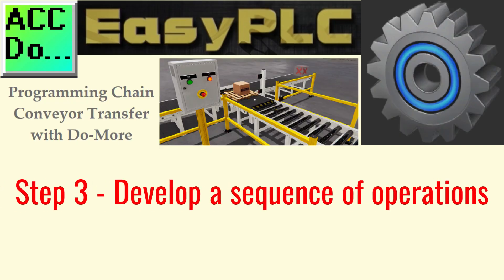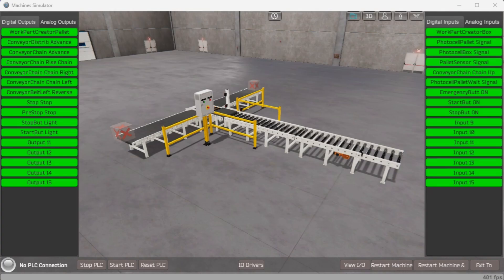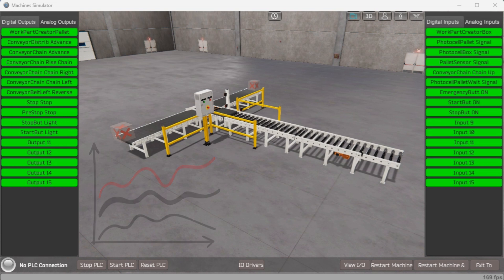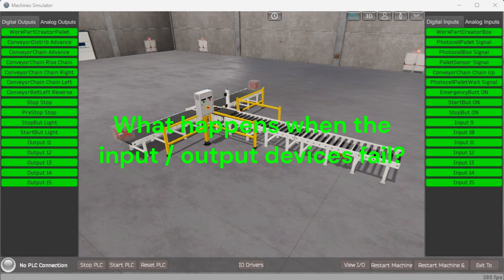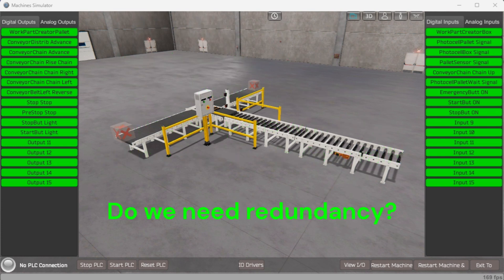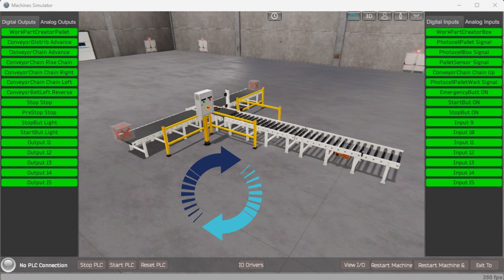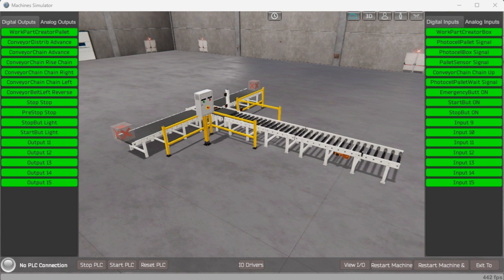Step 3: develop a logical sequence of operations. This step is used to thoroughly understand the process that needs to be controlled. It must answer questions like: what happens when electrical power or pneumatic air is lost? What happens when input and output devices fail? Do we need redundancy? This step is where you can save a lot of work by understanding everything about the operation. It will help prevent you from continuously rewriting the PLC program logic. Knowing all these answers up front is vital in developing the PLC program.